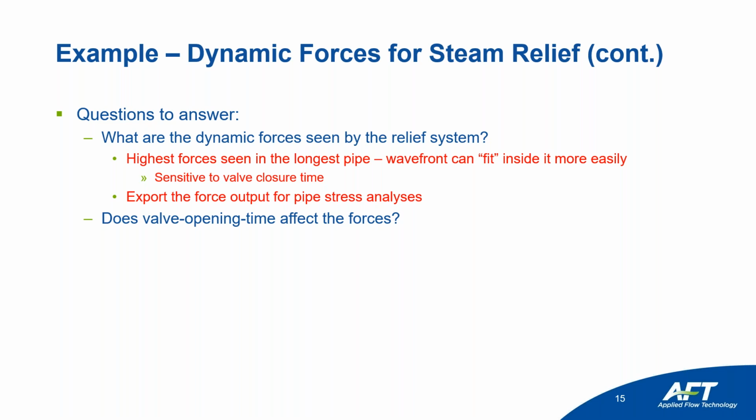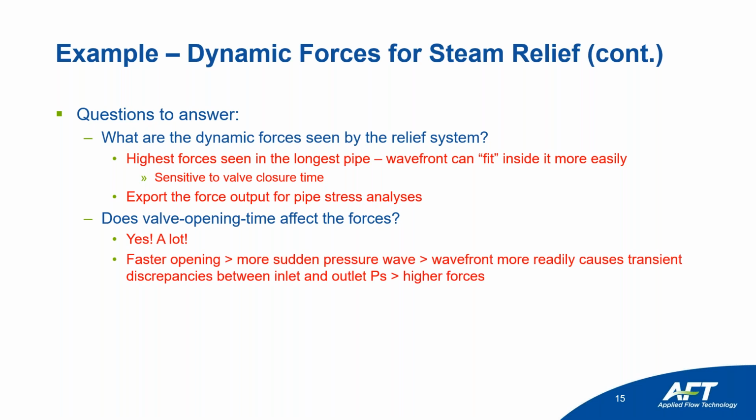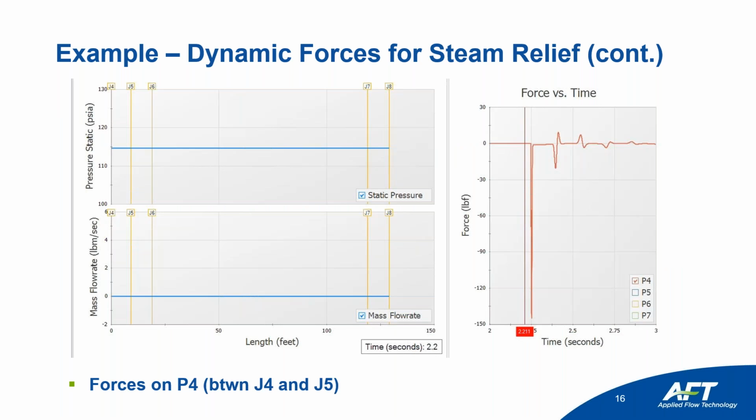Does valve opening time affect forces? Yes, a lot, for the reasons we explained. Faster opening, more sudden pressure wave. The wavefront more readily causes transient discrepancies between the inlet and outlet. In other words, it fits inside of the pipe. That leads to higher forces. Even if things like maximum pressures are similar, forces can be very different. And that is a major point to highlight. And it's all about that wavefront.